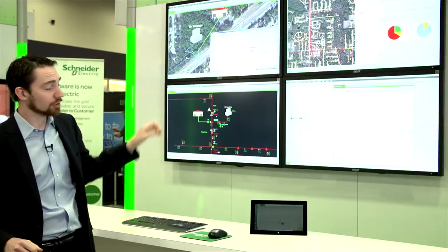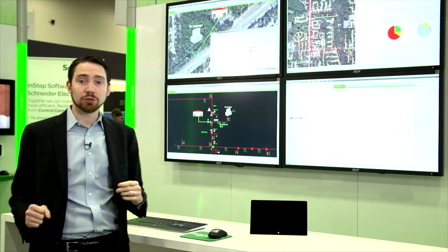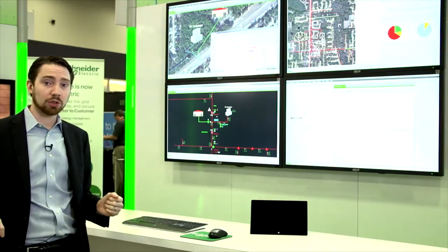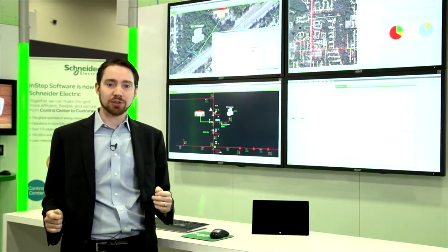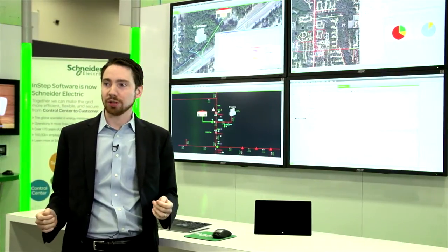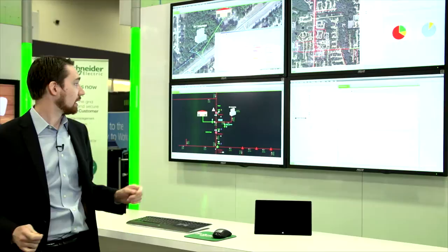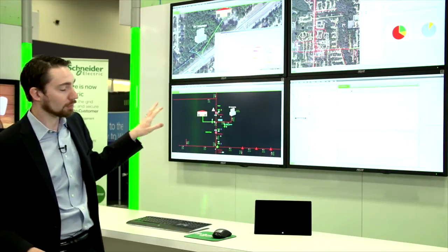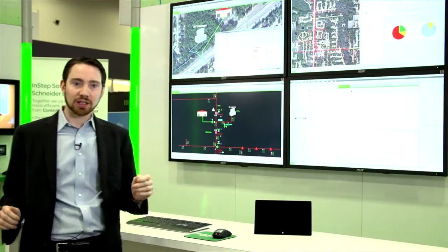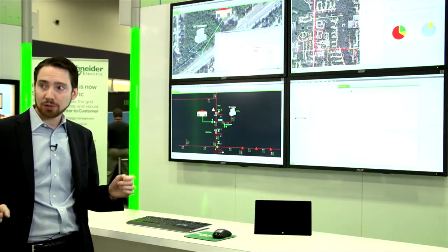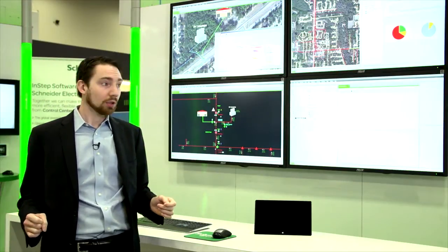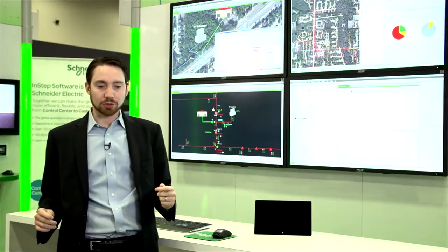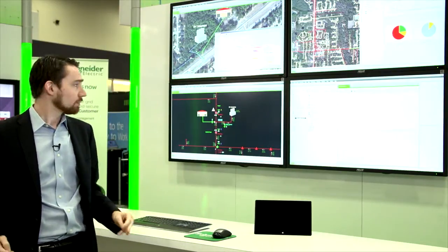Once we have all this information, we can start to do some pretty powerful functions. One of these functions we call FLISR — Fault Location, Isolation, and Supply Restoration. The benefit is that it allows you, the utility, to have your system automatically locate faults, isolate them, and resupply as much power as you can before a critical event happens, or whenever you're going in to do outage management.